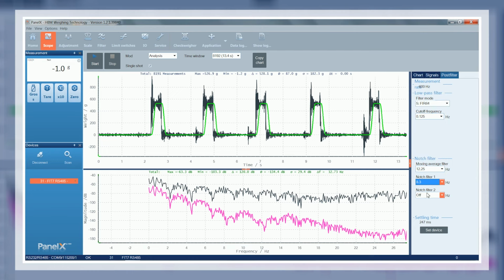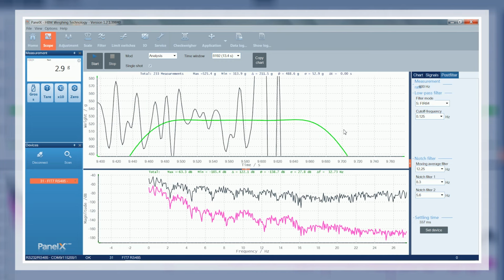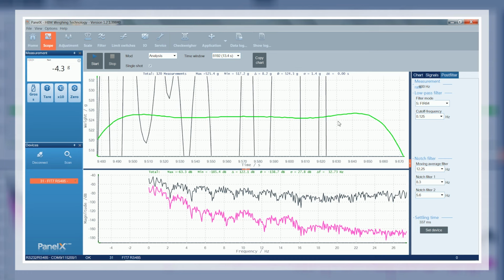The two-notch filters can be applied the same way as the arithmetic mean filter. They suppress frequency ranges of around ±2 Hz by the specified filter frequency. Next, we will dial a filter frequency that is about 2 Hz lower than the maximum frequency, contributing -100 dB to the signal. The processed signal will once again improve significantly after the filters are applied, and our resulting plateau levels out even more. We have found very good values for the processing of our raw signal and will transfer these to the electronic array of our FIT7A.